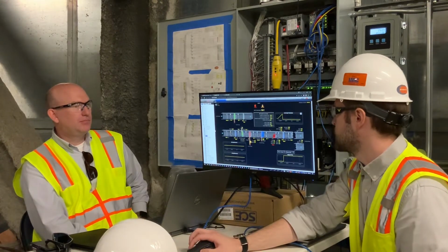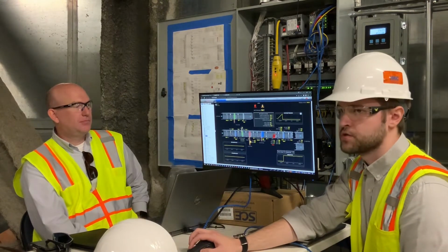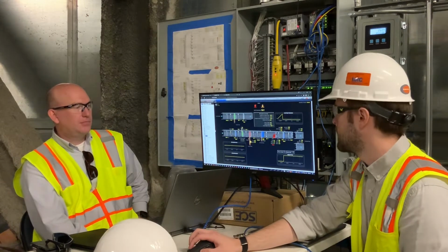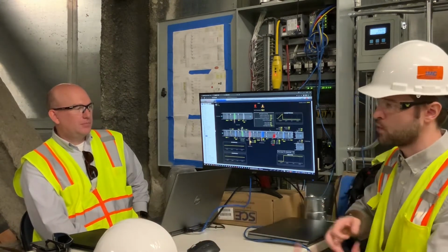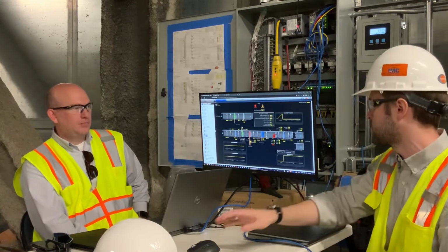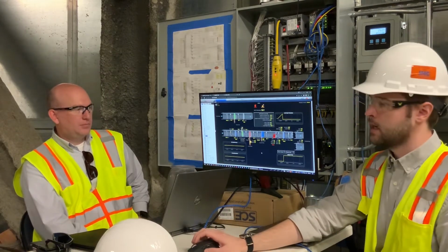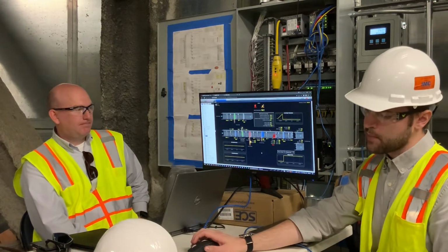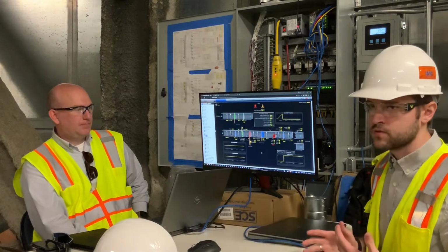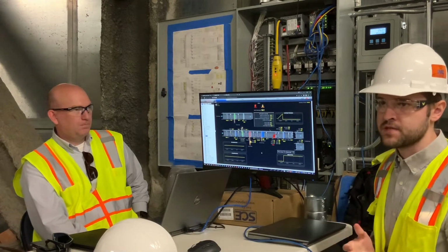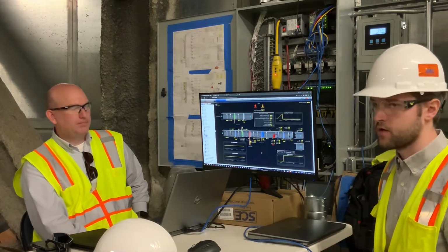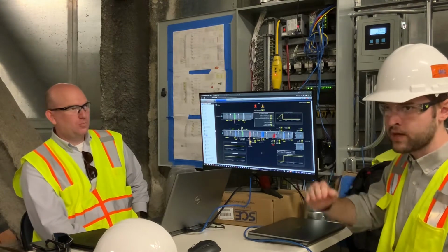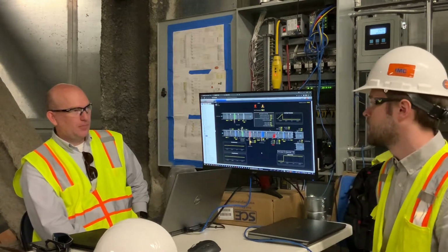Other than that, this unit is extremely similar to air handlers 1 through 4. It doesn't look for set points from other units. It has its own set points right on the unit. I believe there's a reset on the static pressure set point. So based on demands from the space, from the Phoenix equipment, and from our equipment, you'll see that pressure set point increase and decrease.